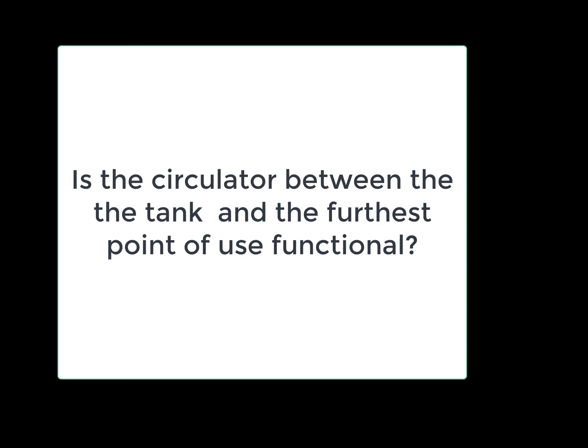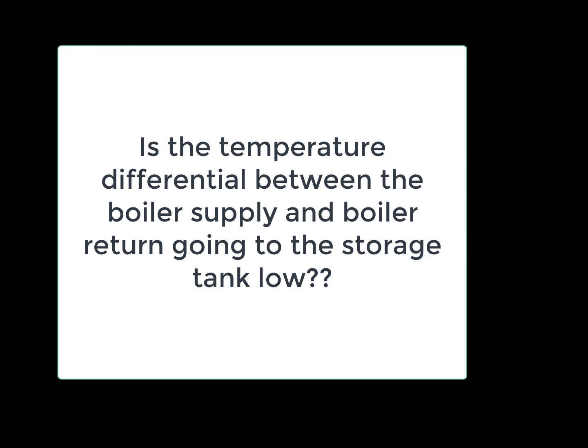It's constantly changing. The simple way to test this and confirm it is to close the circulation return line off and see if the temperature stabilizes. If it does, you have a bad check valve. If the customer complains that the storage tank is very slow in recovering, and you see a very low differential in temperature between the supply and the return line, that's an indication that the heat exchanger that's immersed on the inside of the storage tank is completely lime scaled up. This basically retards the flow of heat from the boiler water through the heat exchanger and into the potable water. If that is the case, it will be necessary to treat this heat exchanger with acid in order to remove the lime scale accumulation so that it has good conductivity to the surrounding water.